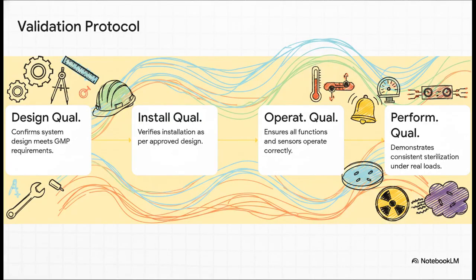And to ensure the equipment actually hits those mathematical targets every single time without fail, engineers follow this incredibly rigorous layered testing protocol. First up is design qualification, basically ensuring the blueprint meets all the safety standards. Next is installation qualification, proving the machine on the floor was built exactly to those blueprints. Then comes operational qualification, where they take every single sensor, valve, and alarm and test them at their absolute extreme limits. And finally, the ultimate test, performance qualification. This involves running actual test loads that are deliberately spiked with tens of thousands of highly resistant bacterial spores, just to prove, beyond a shadow of a doubt, that the machine can completely obliterate them.